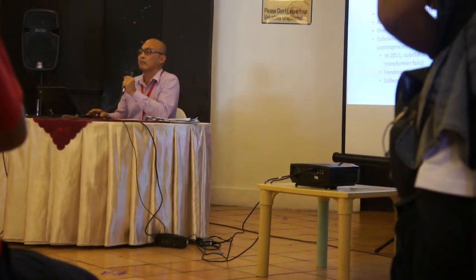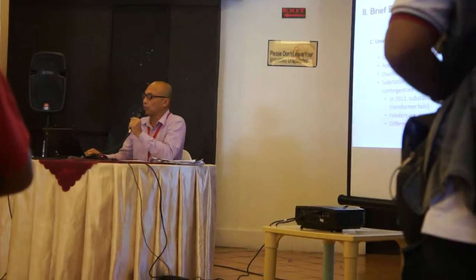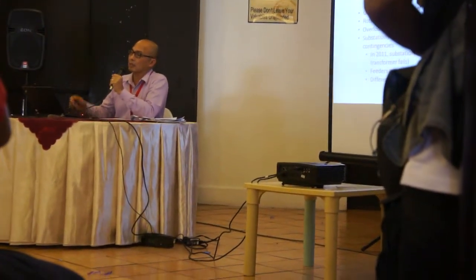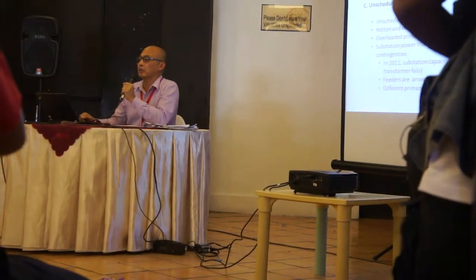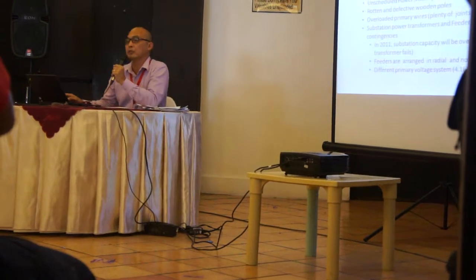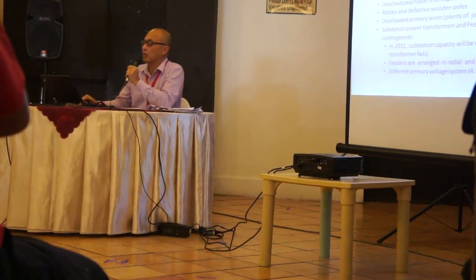Then another problem is that the substation power transformers and feeders are not capable of handling N-1 contingency. In the distribution utility operation standard, the ERC, the regulator, allowed N-1, meaning if we have 5 transformers, or 5 substations, and one substation goes down or fails, the remaining capacity of the system should still be capable of serving the load. That's N-1 contingency. The idea is that it takes time to replace a power transformer, about 1 year. That's the reason why the regulation allows the distribution utility to have N-1 contingency as one of the planning criteria.